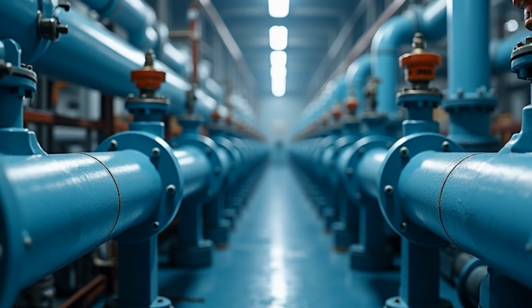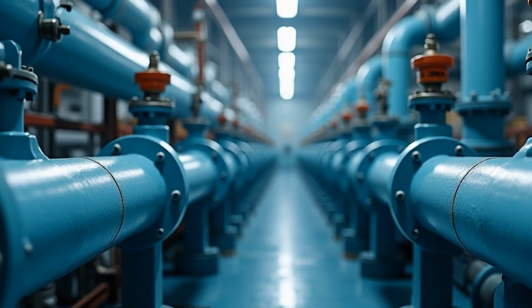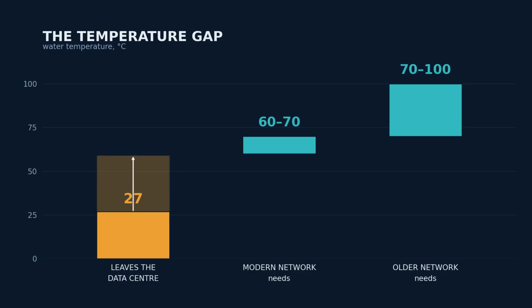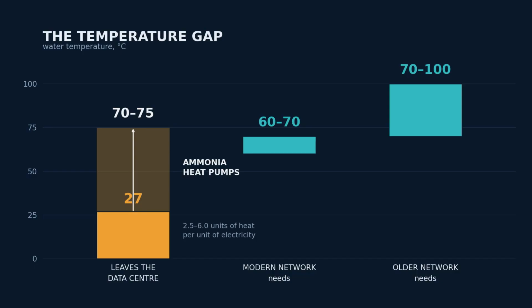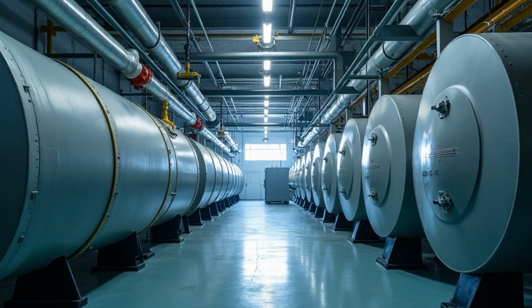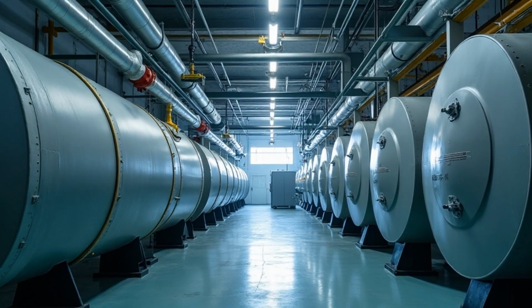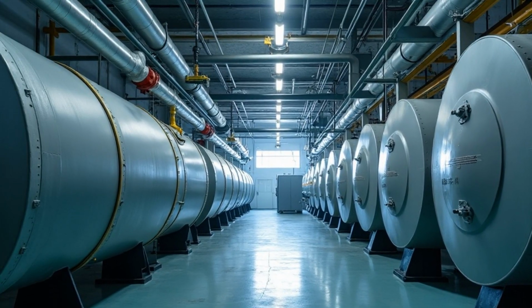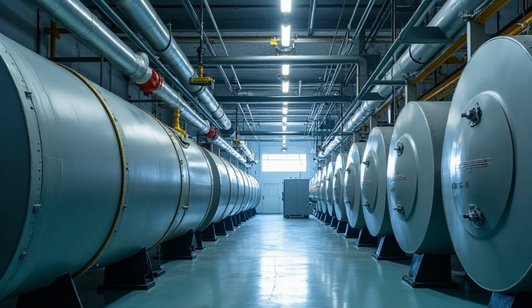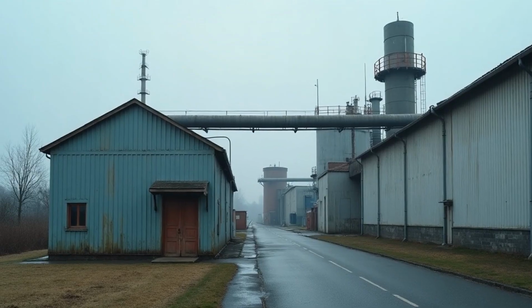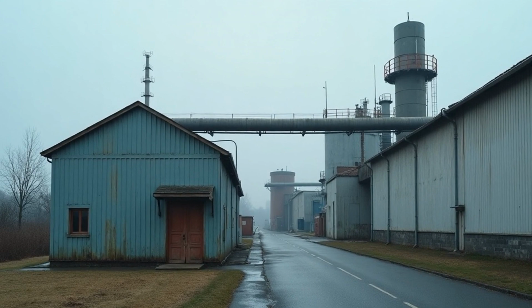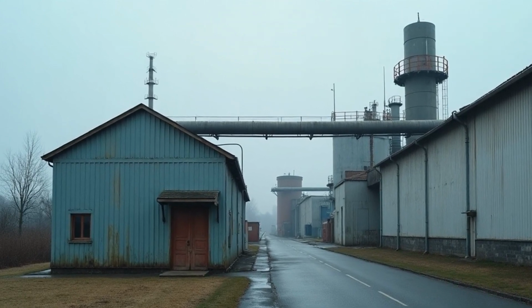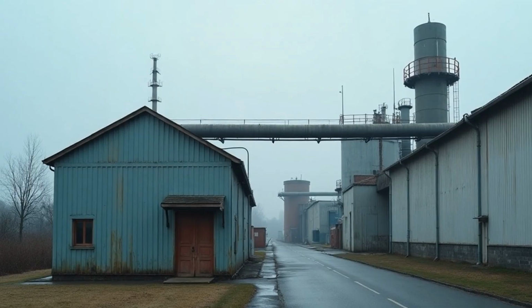Next to the site sits a station of large ammonia heat pumps. A heat pump takes low temperature heat and pushes it higher by spending electricity. That plant lifts it to 70, 75 degrees, what the network will take. It works. It is not free. On that lift, you get between 2.5 and 6 units of heat per unit of electricity spent. Look at what got built here: an industrial plant, ammonia compressors and all, whose only job is turning warm into hot.